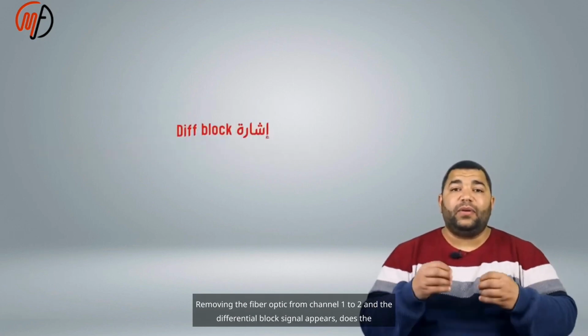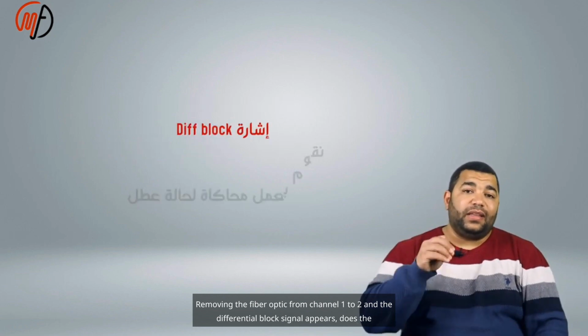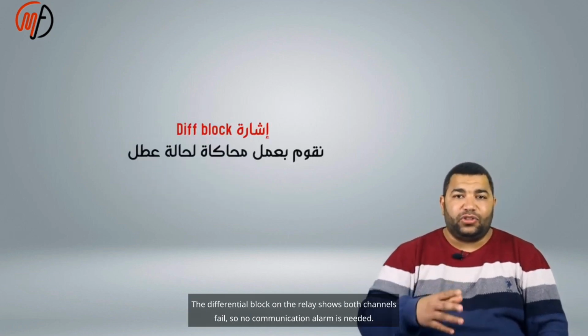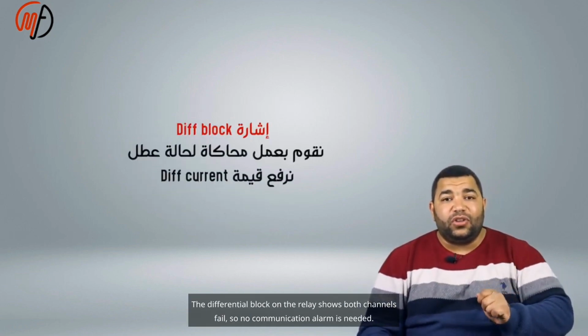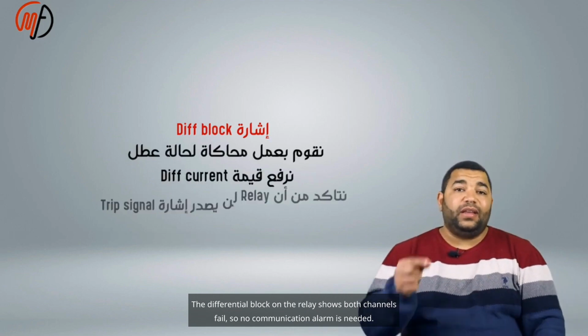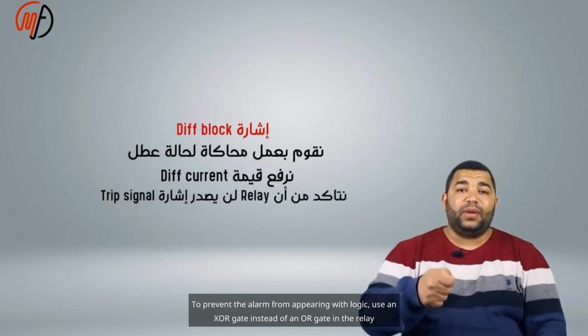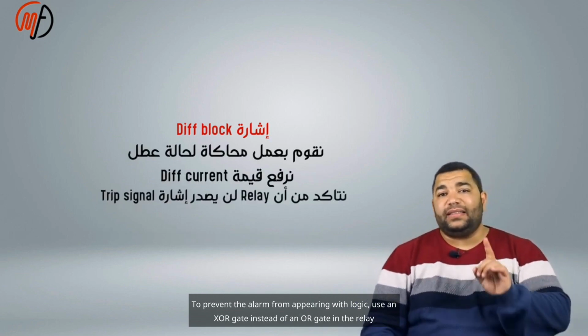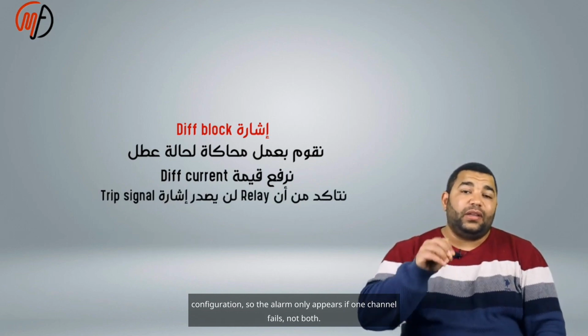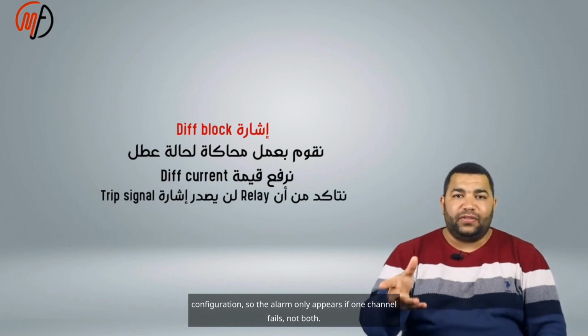Removing the fiber optic from channels 1 and 2, the differential block signal appears. Does the communication alarm show? The differential block on the relay shows both channels fail, so no communication alarm is needed. To prevent the alarm from appearing with logic, use an XOR gate instead of an OR gate in the relay configuration, so the alarm only appears if one channel fails, not both.